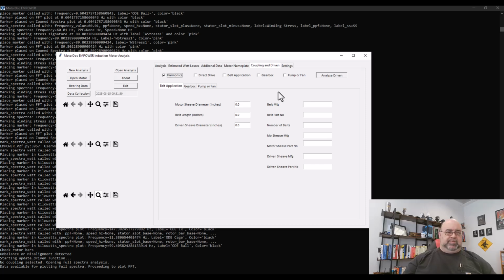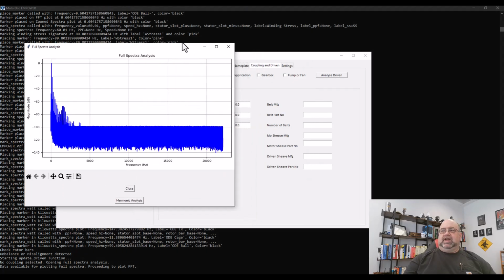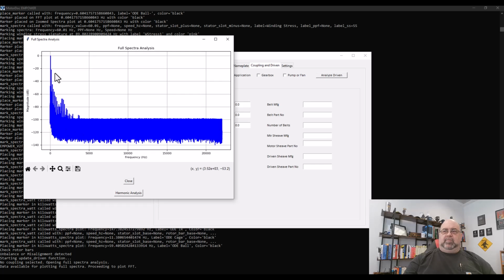And it should pop up any hour now. Here we go. Okay, you can see it's not on a VFD because all my harmonic content sits right back here and dies off, and it's at 100 dB down, so that's really good. On a VFD, it's going to be sitting up here somewhere.